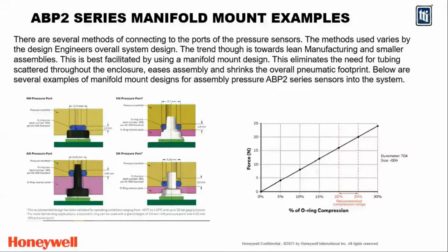The other trend we're seeing is that a lot of our customers are going more towards the manifold mount design. What we mean by that is you have a sensor and an O-ring, and then you plug it into either a plastic or a metal manifold, rather than using the historic tubing method of attachment. The advantage of a manifold is it leads towards lean manufacturing. It leans towards smaller assemblies since you don't have tubing running all over the place, which takes up space. And it's lean, and good for poka-yoke, because you're less likely to put a tube in the wrong spot. If you've got 5 tubes and you connect one to the wrong sensor, you've just created an issue in your assembly. So this eliminates that type of event from occurring.